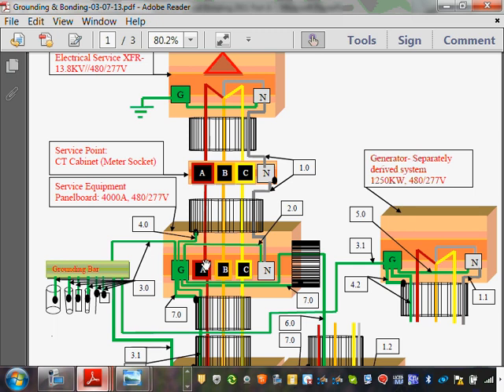This is the 4.0. When you bring your rigid conduit to the bottom of that switchgear, you're at the service, so you need to bond the conduits to your enclosure. The conduits bringing the service, if they are metallic, need bonding; if they're PVC, don't listen to me. If they're rigid, intermediate, EMT, any metallic wiring methods, you need to bond the conduit to the ground inside your switchgear. That bonding has multiple ways you can do it.